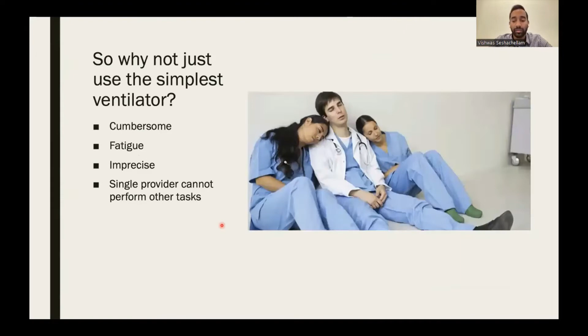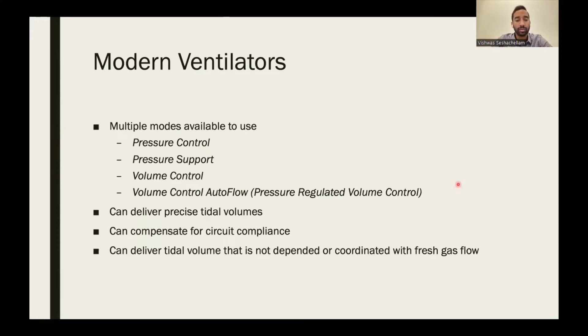With our modern ventilators, there are multiple modes available to use. They can deliver very precise tidal volumes. They can compensate for circuit compliance and deliver tidal volumes that are not dependent on or coordinated with fresh gas flow. This is a very big change. Previously, fresh gas flow would be a factor of what tidal volume is delivered, inspiratory time. Now this can all be independent and the machine will deliver exactly what you set the machine to. Multiple modes are available to use. A couple that we'll be talking about today are pressure control, pressure support, volume control, and volume control auto flow, also called pressure regulated volume control. And we'll define these now.